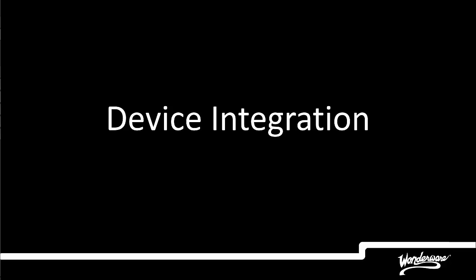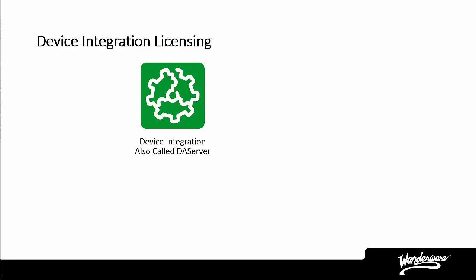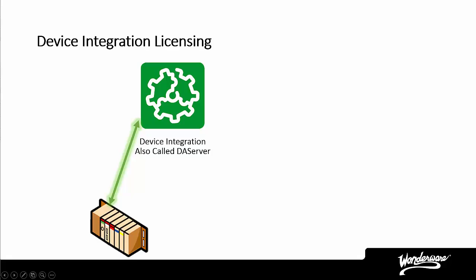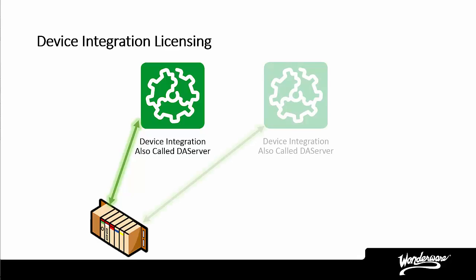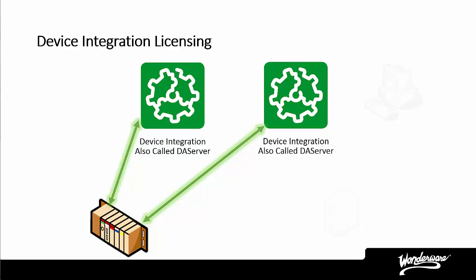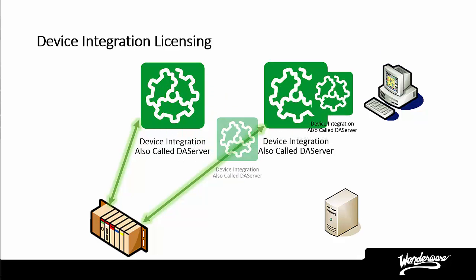The next software product we will discuss is the Wonderware Device Integration Servers, also called Data Access Servers or DA Servers. These DA Servers allow the Wonderware software to communicate to the PLCs and devices in the system. There are many different DA Servers because there are different PLCs and device vendors, most using different communications protocols. You can have multiple DA Servers in your application if communicating to different vendors or protocols, and you may also have two DA Servers of the same type to provide redundancy or failover. Each computer where a DA Server is installed must have a device integration license; however, one device integration license can enable multiple DA Servers on one computer.